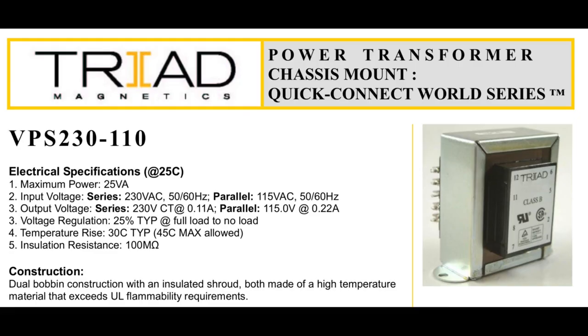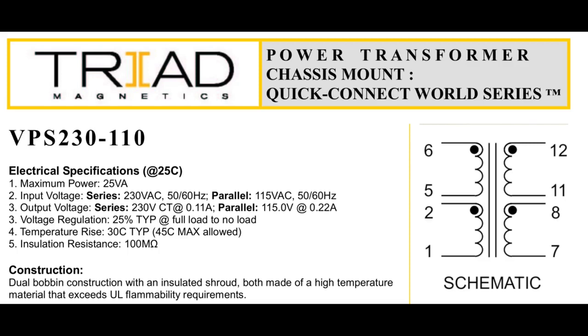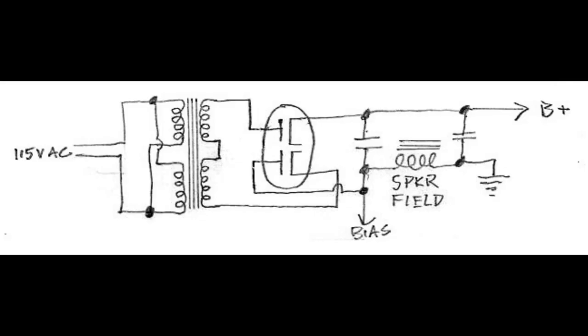When I found this isolation transformer from Triad for $11, I was pretty excited because the form factor exactly matches the original from the radio, and it can be wired for either 115 or 230 volt secondary. What I didn't realize is that these isolation transformers actually boost the voltage a bit to compensate for losses at full load. So with a 120 volt input and no load, this transformer's secondaries each put out 140 volts. Wiring the secondaries in series would produce 280 volts, which is way too high.